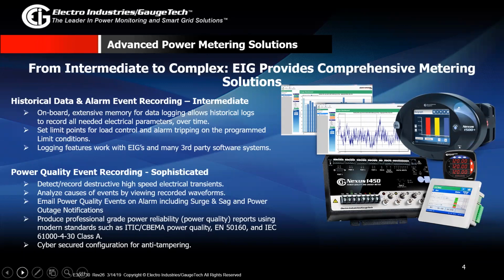A step up from the intermediate level, a full-blown Nexus meter will give you very sophisticated power quality event recording. What I mean by that is it will detect and record very high-speed electrical transients. Even those transients that occur over a very, very short amount of time, the Nexus meters have the capability to capture that data and not miss any of your high-speed electrical transients. It can also take waveforms up to very high sample rates, which I will get into in more detail down the line, so that you can look at your waveform data and analyze the root cause of your power quality issues.